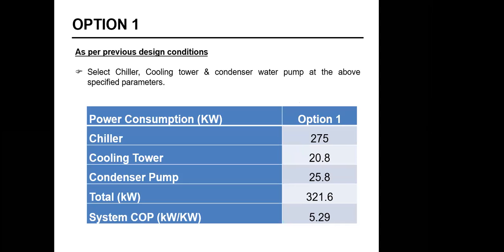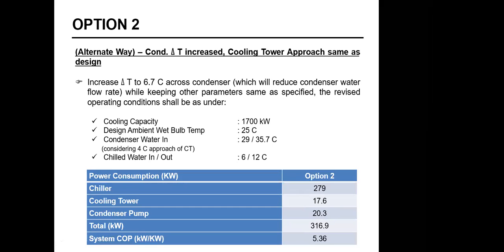Now every manufacturer has selected the equipment based on these design parameters. So what comes out is, the chiller which I selected is consuming 275 kilowatt input power. The cooling tower which has been selected is consuming 20.8 kilowatt. The condenser pump is consuming 25.8 kilowatt. So that is the total kilowatt consumed by the chiller plant, excluding the chilled water system, which I'm not talking about today. The COP, or the efficiency of the plant, becomes 5.29. This is basically 1700 kilowatt divided by 321.6. We call it system COP. This is the standard offer which a designer or consultant would get if we limit ourselves to the design parameters only. Now, as an alternate way, he allows some flexibility to the manufacturer, so that you try to select the best optimized pump, cooling tower, and best optimized chiller.